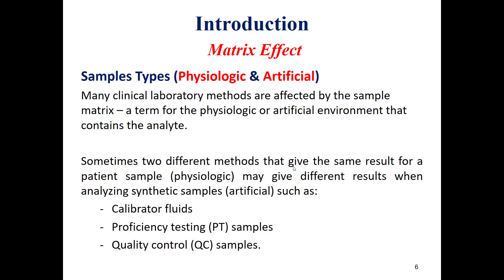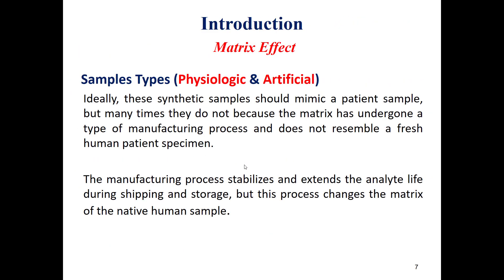Sometimes two different methods that give the same result for a patient sample may give different results when analyzing synthetic samples such as calibrators, proficiency testing, and quality control samples. These synthetic samples should mimic the patient sample; however, many times they do not because the matrix has undergone a manufacturing process and does not resemble a fresh human patient specimen. The manufacturing process aims to stabilize and extend analyte life during shipping and storage, but this process changes the matrix of the native human sample.